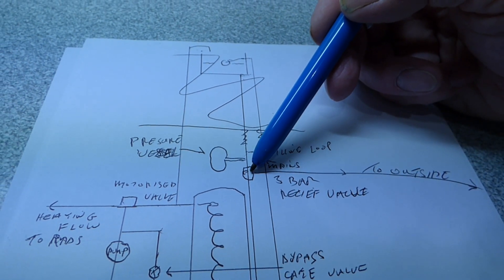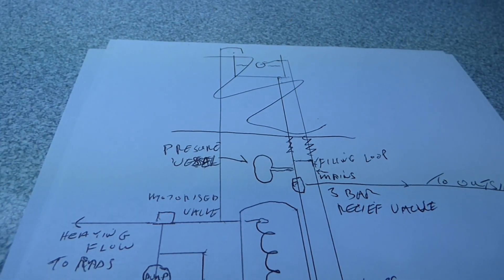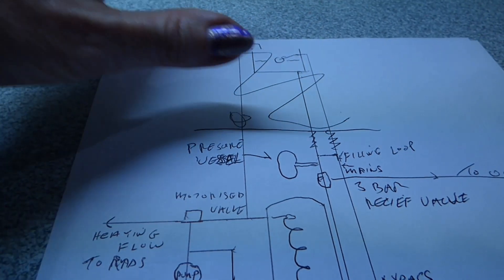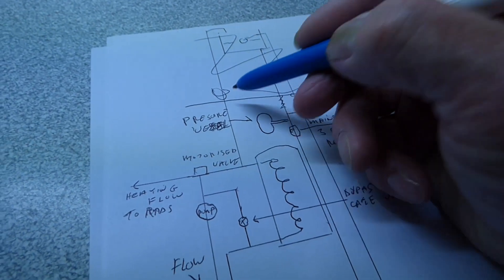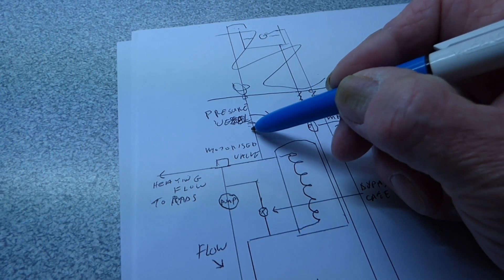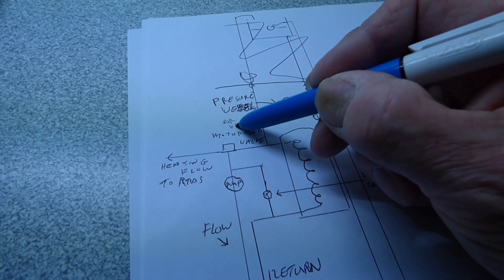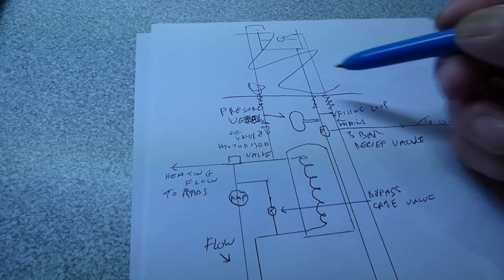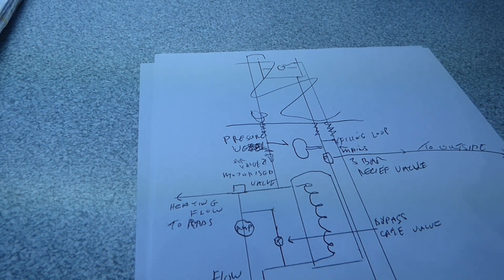You put your vessel on basically and then what happens is you take down to this relief valve that's just, it's an emergency really, because if you went over three bar, obviously it would be dodgy. So the idea is, a bit like a combi boiler, it's got to be kept down probably to about one bar, 1.2 to 1.5. If you over pressurise it, obviously it would then open and the water would run outside, so taking the pressure out of the system. So sorry, so what about this piece of pipe here that goes up? Yeah, it's cut off. So it's cut there, so what would you just cap it off, plug it off? Yeah, this one here, what we'd do with this one, actually I did forget to show it properly, what would be best here, as it comes up off the cylinder, would be to cut it there and have an air valve on there. So we'll pull that down, shall we? Yeah, that makes more sense. On there. So that pipe is now gone, okay, and you've got your air valve on there to release any air out of the top of the system there. I should have included that, so well said. Yeah, part of the drawing.